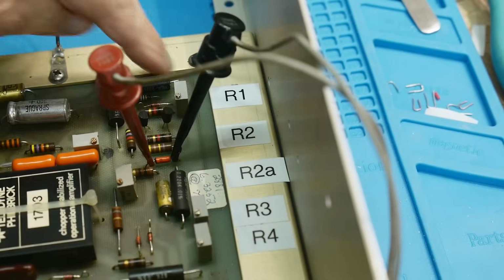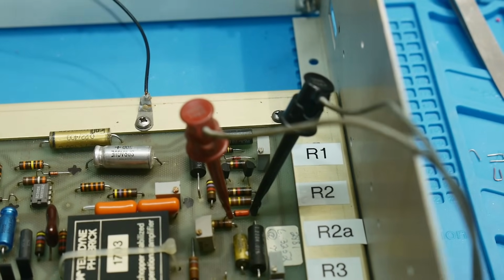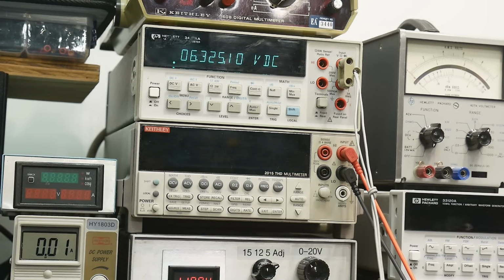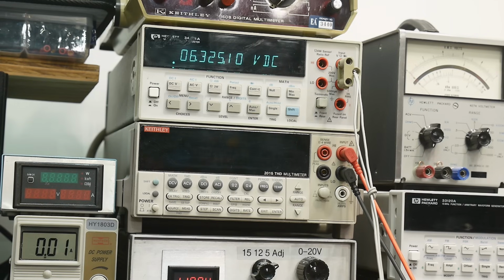I've labeled them. So R1 is up there, and these R numbers match the schematic, which I'll show you in a bit. Let's adjust this to 6.35. Let's see, what is it? 6.3251. Okay, so we want to move it just a tiny bit. Let me get my tool on the potentiometer. Yeah, going the wrong way. Let's see here. Oops. 3, 2, 5. I'll go this way. There, whoop, went too far. Okay, I'm going to say that's close enough. All right, so now we should be in its happy range, okay?